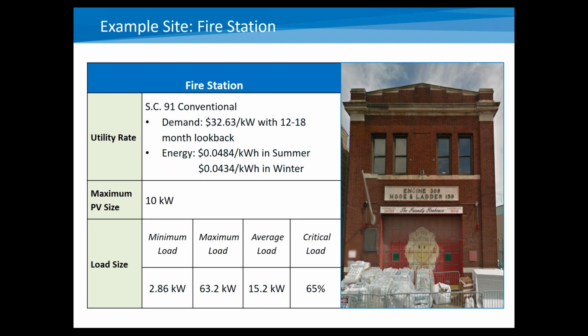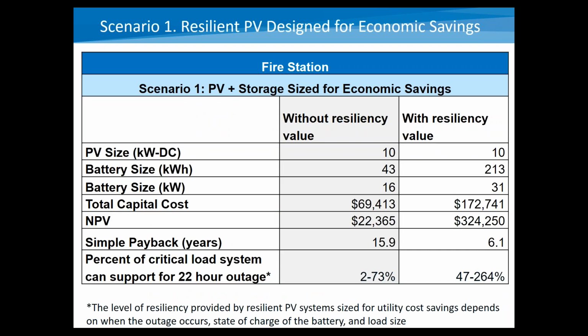Based on the roof area available at this site, the maximum PV size that could be installed was 10 kilowatts. And then the load varied from a minimum of 2.86 kilowatts up to 63 kilowatts, with an average load of about 15 kilowatts. And this was one of the sites where we did not have information on the specific equipment that they needed to run during an outage. So we assumed that the critical load was 65% of the typical load.